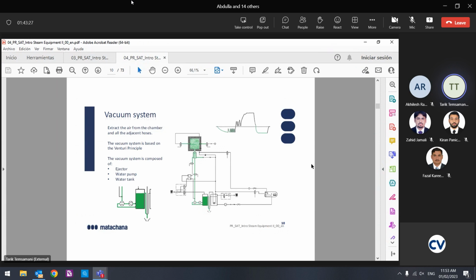Now, if I can't reach this pressure, what can be the possible problem? Gasket. If the gasket is not good and I have a leak, of course I can't reach that, because there is always some air coming into the chamber. More? Pump efficiency, maybe it's less. The pump's performance is not good and it's not reaching the pressure. Pipeline leakage. Non-return valve. If the non-return valve is not opened well, we cannot reach this pressure.